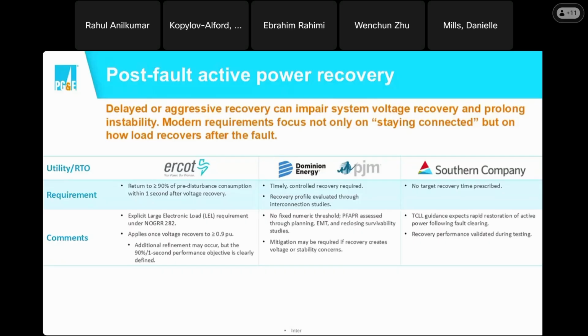And another thing that's also being done is just looking at more aggressive kind of ramping from 0 to the full output, just to understand whether that kind of an event mimics something that you would see if you were to lose a generator, which of course has its own impacts on the frequency. And we're always used to thinking about under frequency, but how do we now start thinking about over frequency, right? And those are some of the things that, as part of the study and all of the ride-through curves as well as the recovery post-fault, those are phenomena that will be explored here.